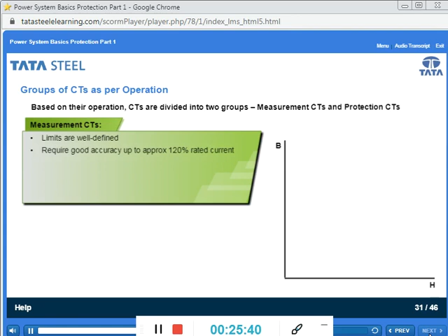Protection CTs operate over a wide range of currents. Accuracy is not as important as above. They require accuracy up to many times rated current. Thus, they use grain-oriented silicon steel with high saturation flux density. The saturation point denoted by Vk is more than that of measuring CT. Now we'll learn about the specifications of CTs.